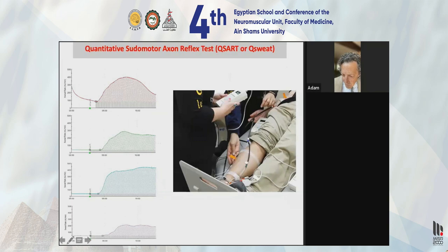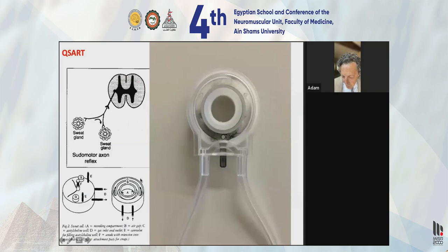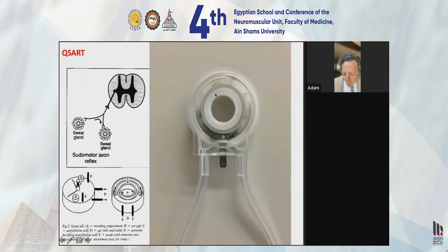The last part of the test is the QSART, measured at four sites. Here is the original QSART diagram by Philip Low, my teacher. Acetylcholine is iontophorized from the outside of the capsule via an anode attached to a battery, and sweating is measured in the middle. This is not the direct sweat response but the indirect, axon reflex sweat response — you stimulate one sweat gland and measure at another sweat gland nearby.